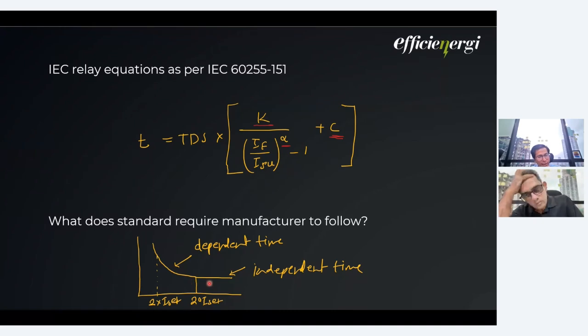There are certain relays where this value can go up to 40 times. That depends on the manufacturer and its manufacturing process. But as per the standard, this is the basic requirement, so most relays you will find working in this region only. After 20 times, we cannot follow this equation. This will be difficult when coordination is required beyond 20 times the set current, when the fault current is very high. That is one challenge we'll cover in our coordination webinar.